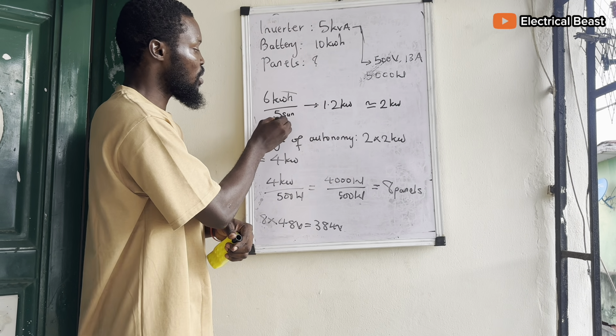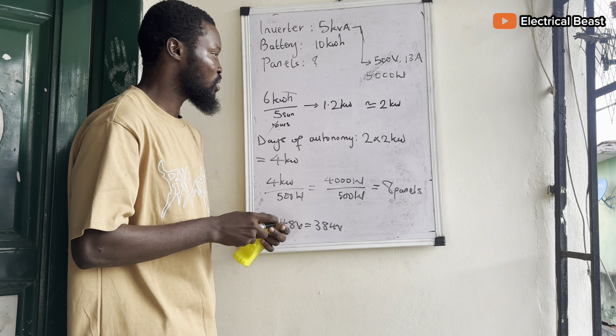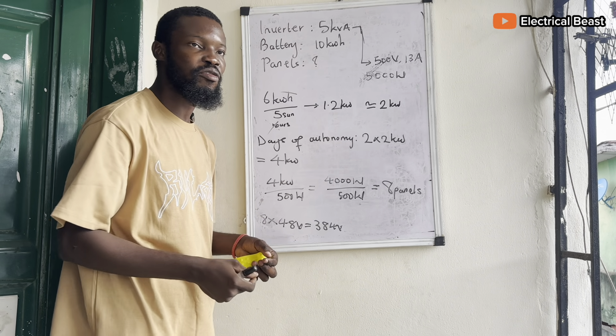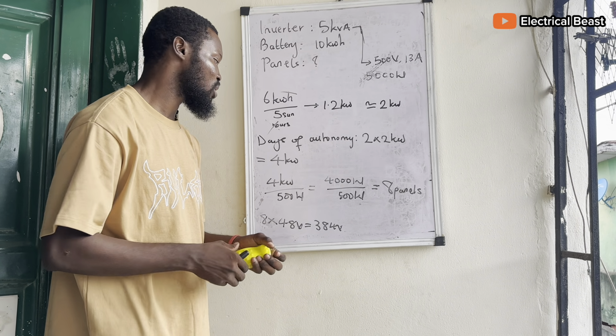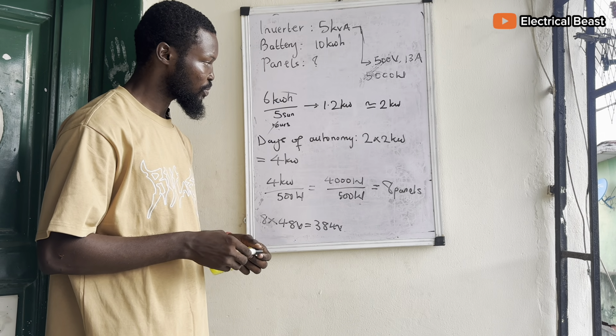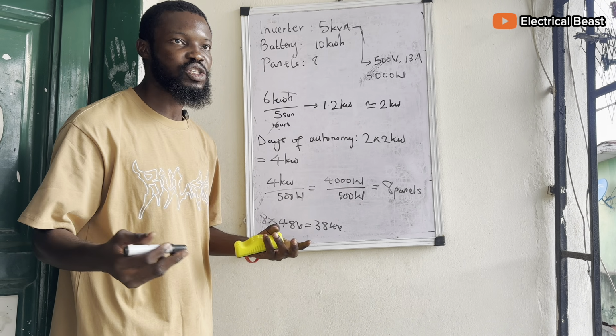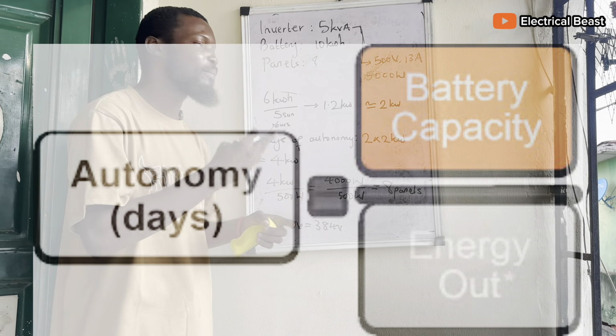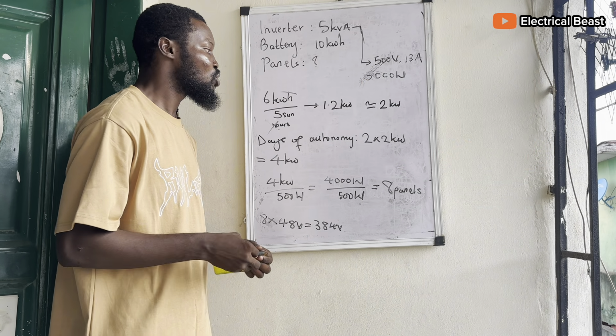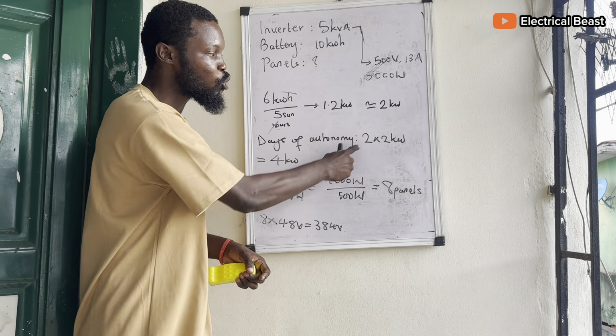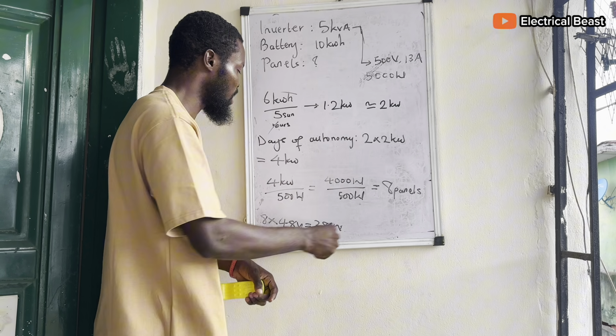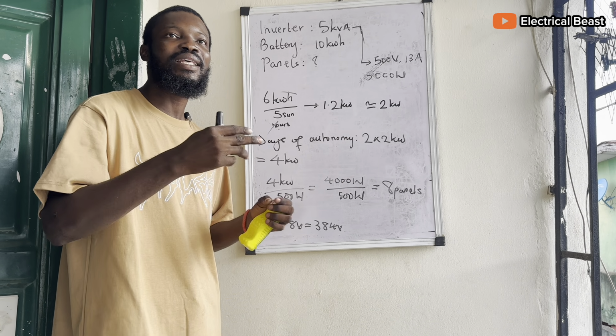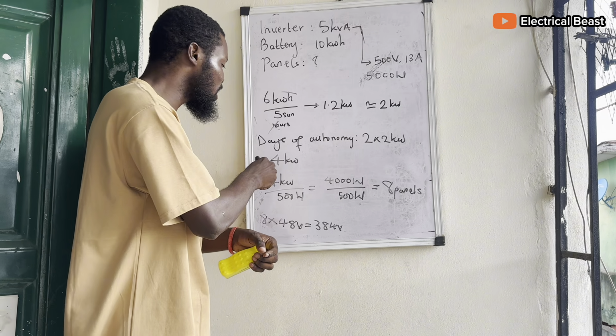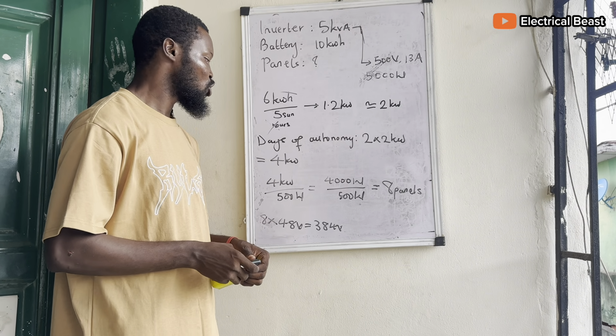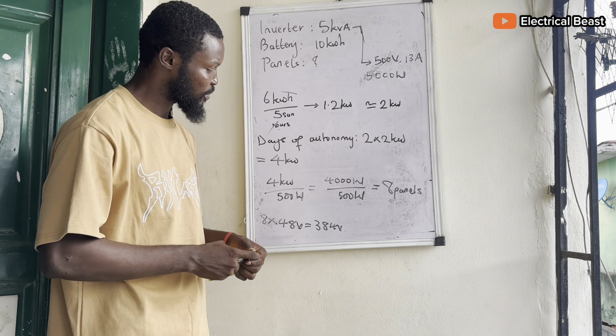Normally, hour cancels hour, so you approximate to 2 kilowatts. You have 2 kilowatts of solar panel array connected together. Now, there's what is called days of autonomy. There are some days where you have rain, cloudy days, so you need to make plans for that as well. Let's assume that the days of autonomy is 2. So you multiply 2 by the 2 kilowatts, you have 4 kilowatts. So your panel array should be able to generate 4 kilowatts at most to be able to charge that battery.